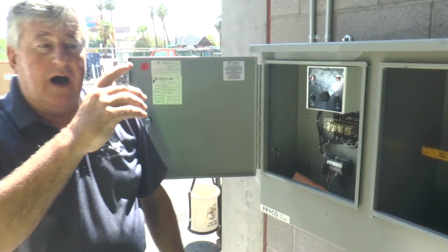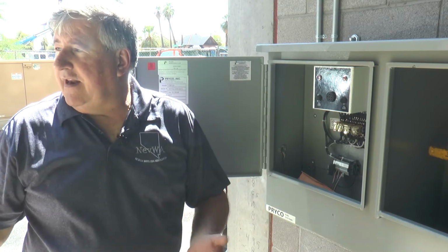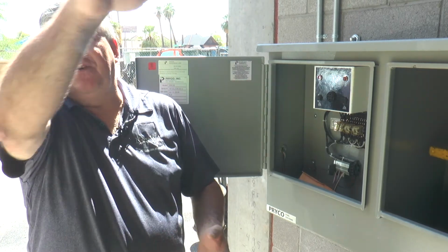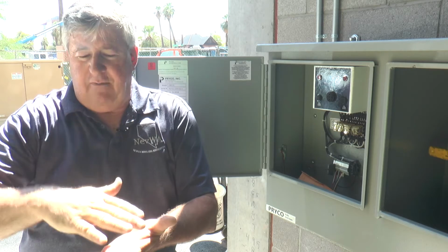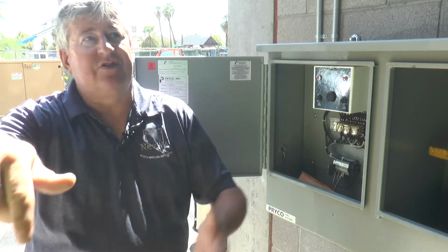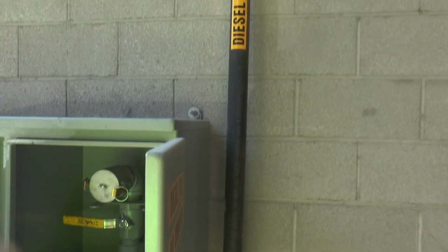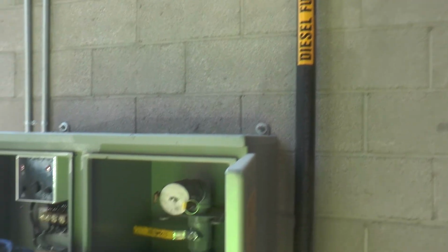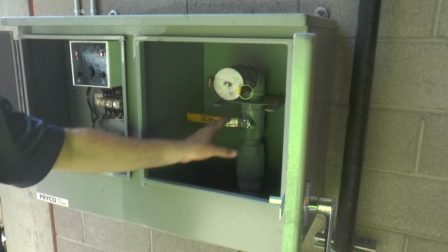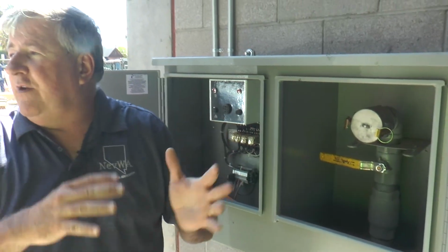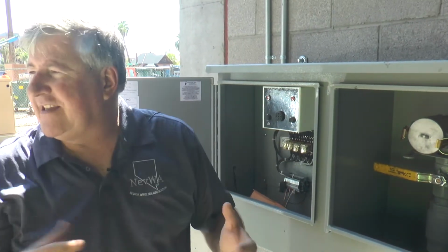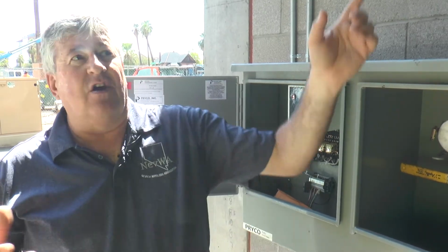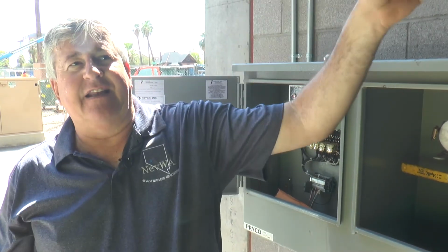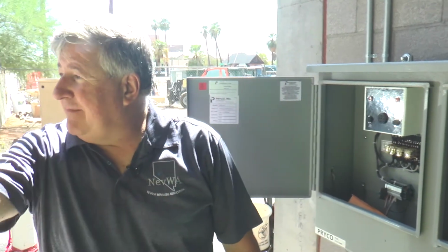Now, when you call for fuel again, or the tank level goes down, if there's any fuel left in the pipe, the solenoid valve will open, and that fuel will eventually drain, since it's on a slope. The only fuel that won't drain back to the tank is right here, but it's being held in place by a check valve, plus a ball valve, so reducing the risk of any spill. And that's what City of Phoenix wants. Oh, absolutely. So any fuel that's left in the line, in that 2-inch line, you probably got another 10 gallons worth of fuel in that line back to the tank.